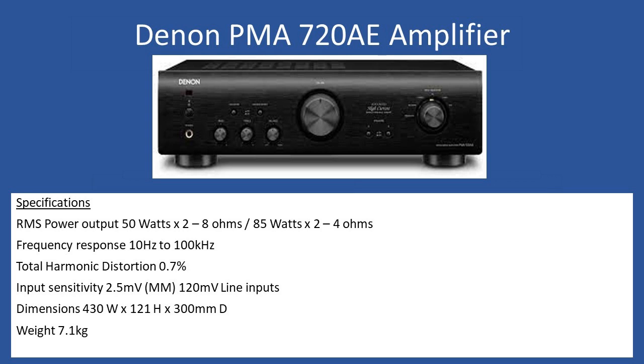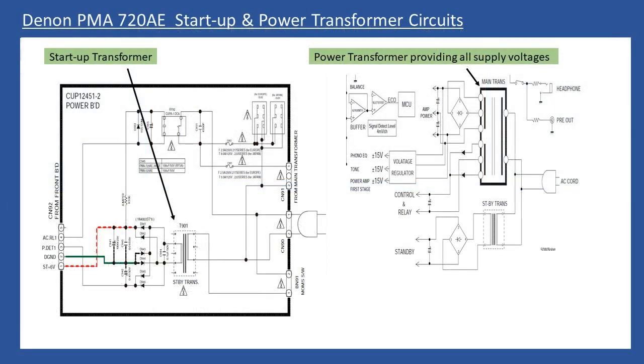So what was the issue with this amplifier? As I alluded a few moments ago, there are some common types of faults with this amplifier, and the most common one is, unfortunately, the failure of the large power transformer. What I'm showing here is an extraction from the service manual - a couple of screenshots showing what we call the startup transformer or startup circuit, and also a block diagram of the large power transformer.